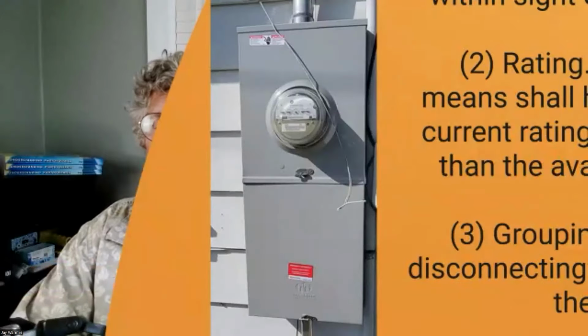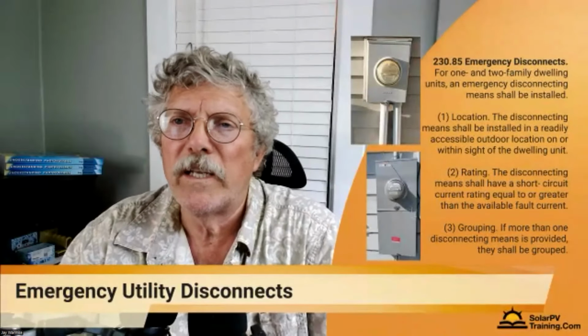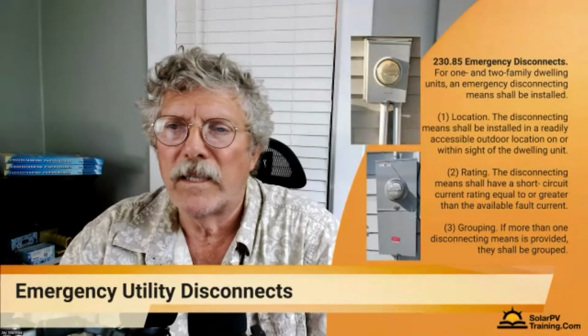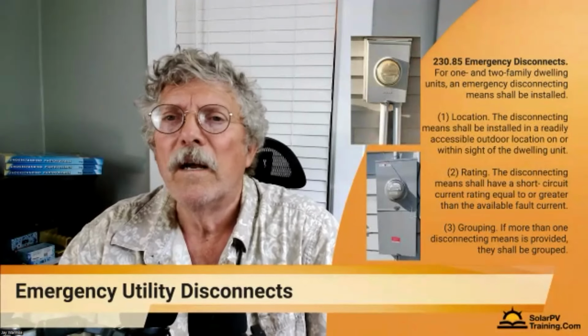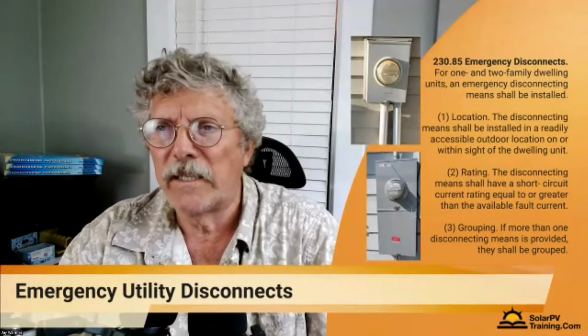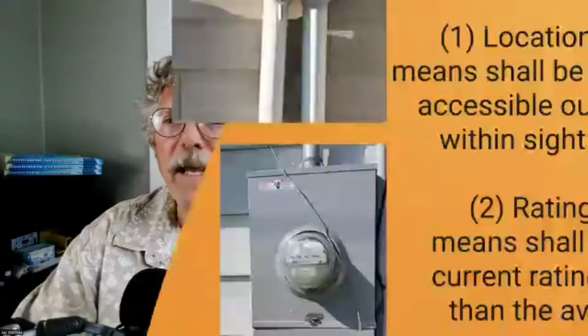I think I had, here in the description, what does that mean. It's in 230.85 about emergency disconnects. And essentially they're just saying that these things have to be out there at the meter, and grouped with other disconnects, which we do that. I don't want to get into that in the solar world, but you put your AC disconnect for your array out there. You put your rapid shutdown disconnect for your battery bank. All of that's going to be out there.